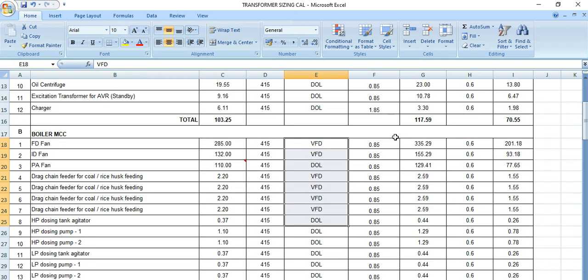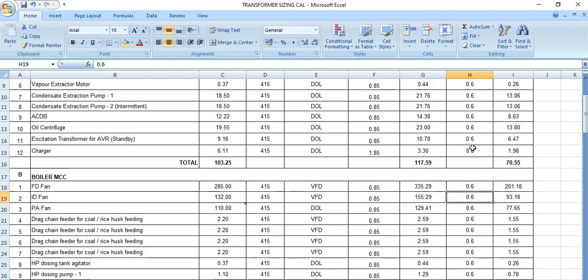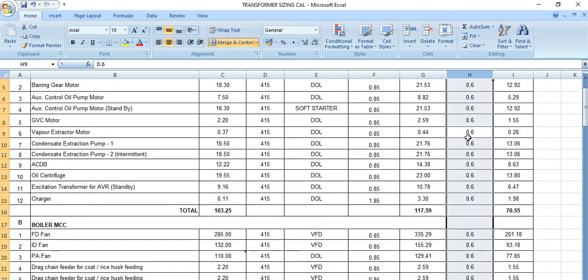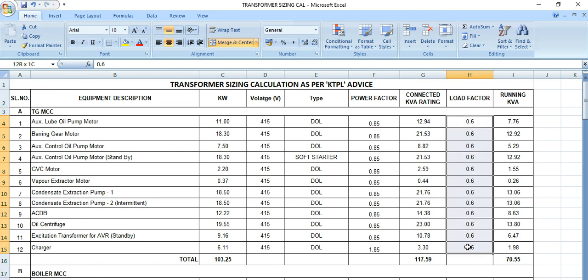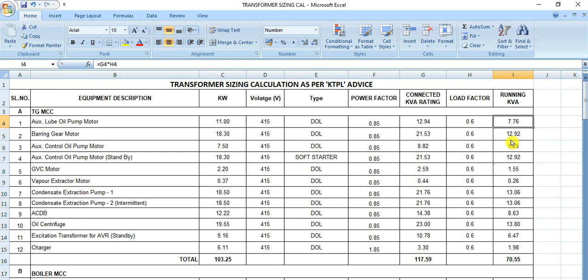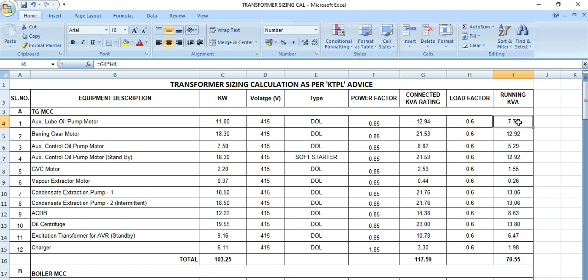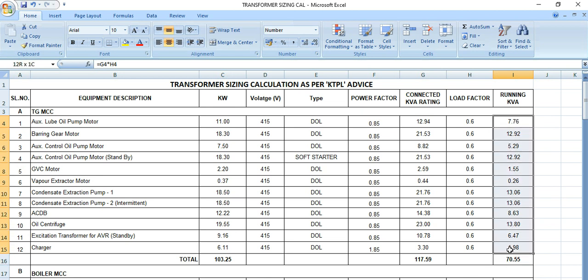And what is the power factor? This H column, this is the loading factor which is considered here, 60 percent. 60 percent loading factor is considered, so the running kVA is reduced because this is the connected load multiplied by this load factor. This figure is coming, which is running kVA, that means the absorbed load you can say.